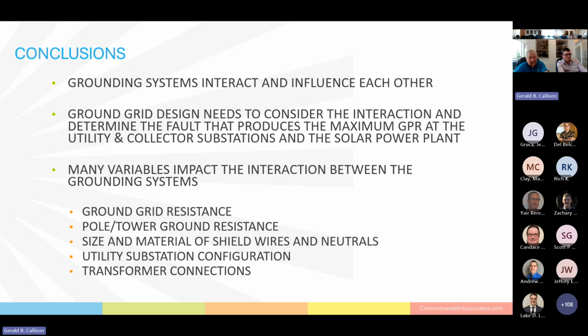The utility substation configuration: you put more lines in, you may have a higher fault current, but you also have more ground path for the current to flow out. Transformer connections can change something, the impedance of the transformers. All of this has an impact on the interaction between the utility, the collector, and the solar or the wind plant. And so that's the whole point of this webinar, to give people an idea that it's not as simple a problem as you might think because of this interaction between the three different entities.